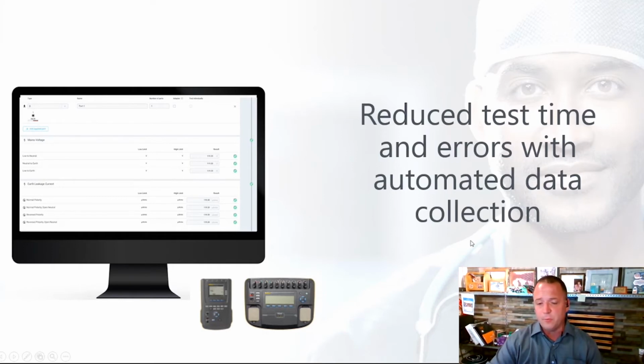Once you start doing those PMs and it's late and cold and you're tired, say your limit on something's 5.0. But if you wrote down 5.01, it technically failed, and you knew you're going to have to go back and either service it or remove the item from service. Removing an item from an OR and saying it's unserviceable isn't always easy, because they're counting on that being in there and working the next day. It's a lot of tap dancing to explain to the doctor that this one was actually found failed, and we had to pull it out, and you can have a lot of upset people.